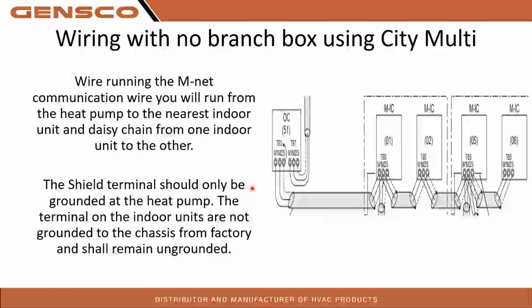All right, so if you guys are doing wiring without a branch box, so you're using City Multi indoor equipment, your MNet communication wire is going to go from your M1, M2 on your heat pump. All of your indoor equipment is going to have an M1, M2 terminal on it as well. So you're just going to run that 16.2 stranded shielded from your heat pump to your first indoor unit, daisy chain right over to the second one, and so on and so forth for all of your indoor equipment. Again, it doesn't have to go to your lowest address, which I'll get into addressing here in a bit, but I would definitely route that the shortest route possible. That way it makes it a little bit easier because there are some wiring limitations, which probably are not going to reach on a residential system, but it's still a good idea just to keep those things as short as you can. And actually, here's my little spot about the shield terminal grounded to the heat pump only. So there's that.